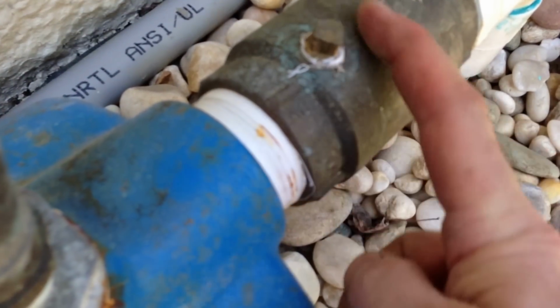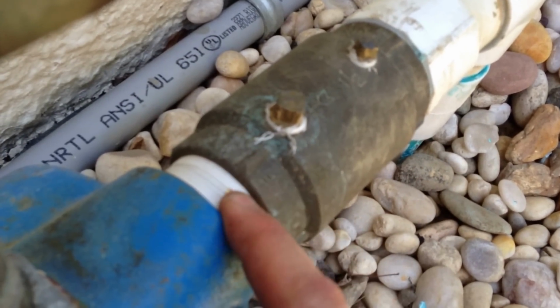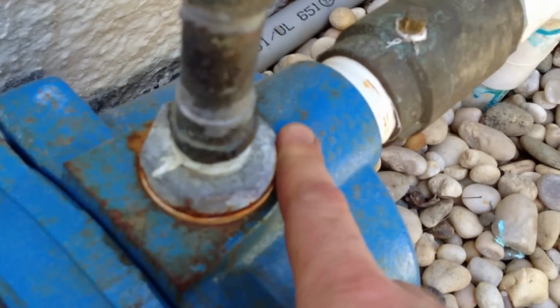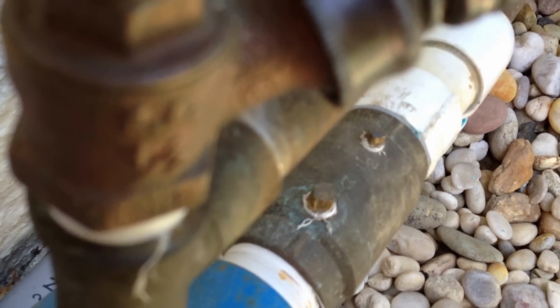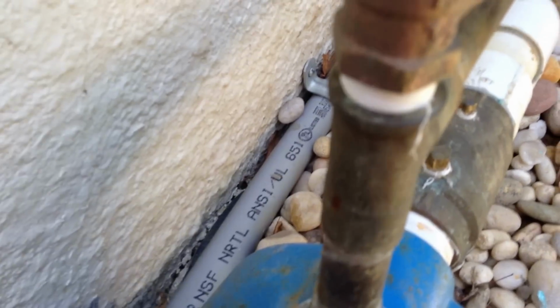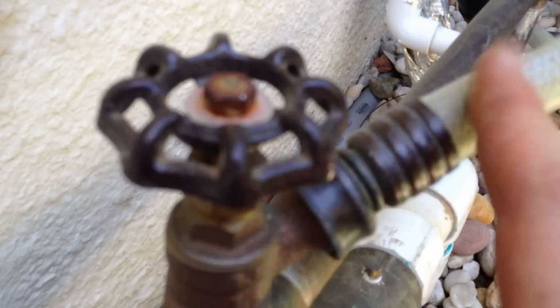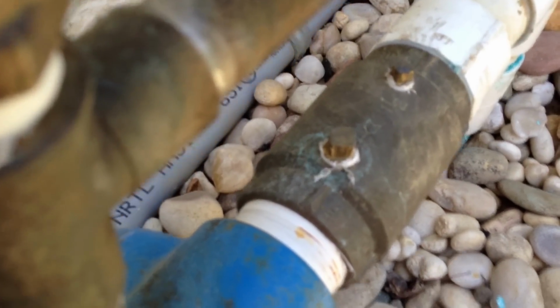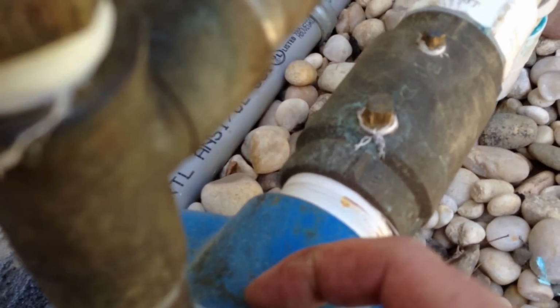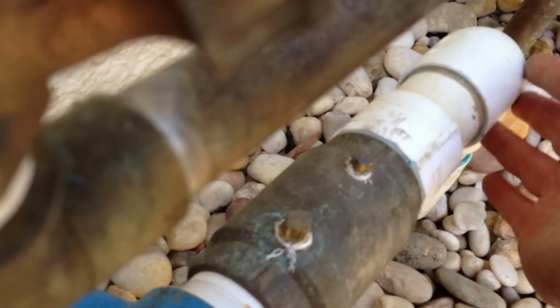This side is after the check valve. It just gives you access to that. A thing to know is when you're priming the pump the first time, it's very difficult to get the water up the first 35 feet. Some people use the opening on top, which in this case is for a garden hose. They pour water in here, and that helps prime the pump. But we've had more success adding water to this side of the check valve. So it feeds the pump when the water comes in, and it's able to create a vacuum to suck the water up 35 feet.